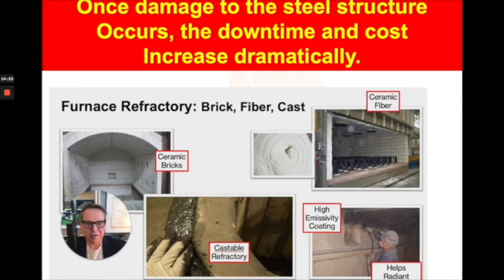There are many different types and styles of refractory. One of the more common problems that leads to refractory failure is folks that start things up very quickly or cool things down very quickly. Carbon steel and rock — which is basically what a lot of ceramic refractory is — don't expand and contract at nearly the same rates. If you heat something up too quickly, the steel outstretches the ceramic material, fractures it, and you then get hot flue gases behind the refractory, which starts to degrade the steel very rapidly. The costs, scope of work, and downtime go up exponentially the longer you wait.